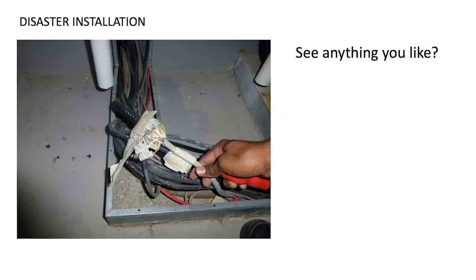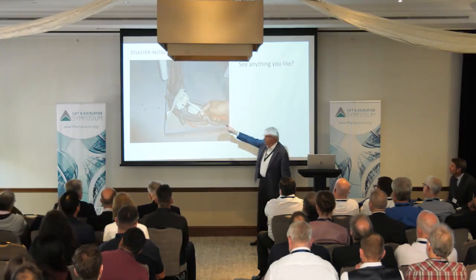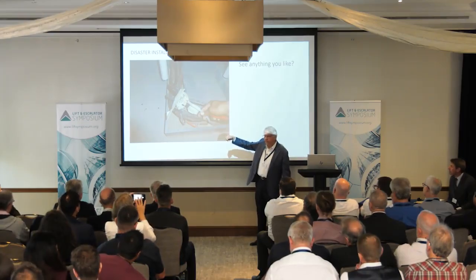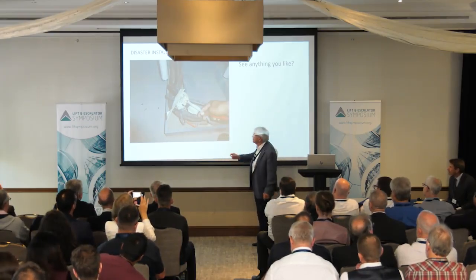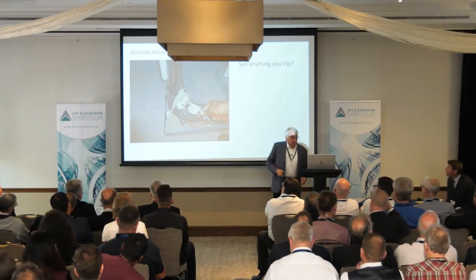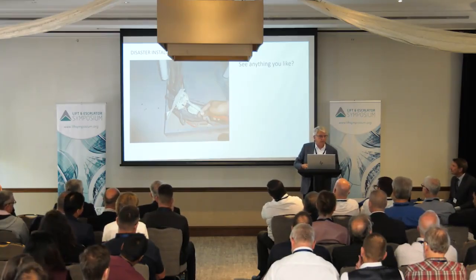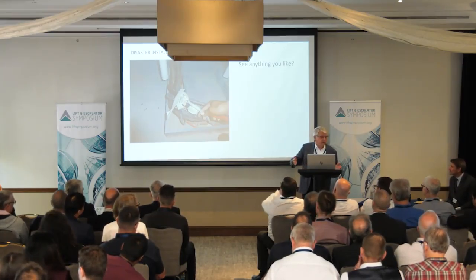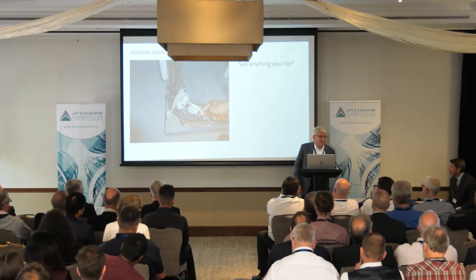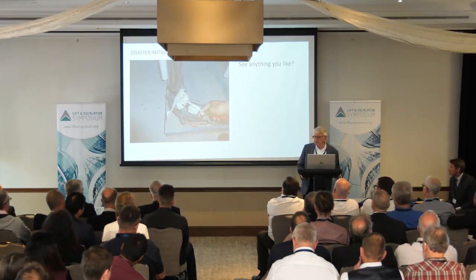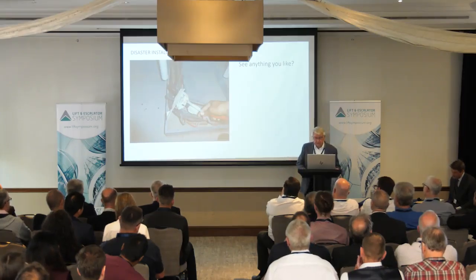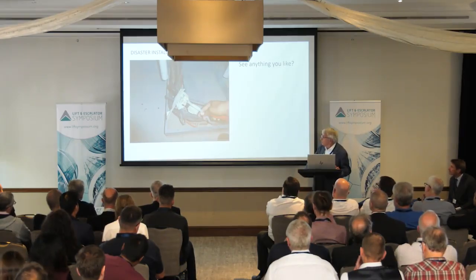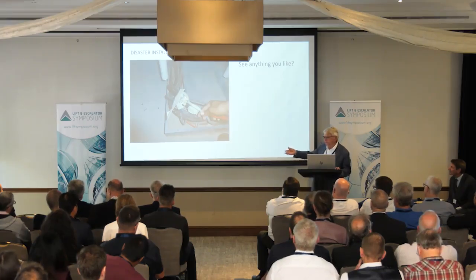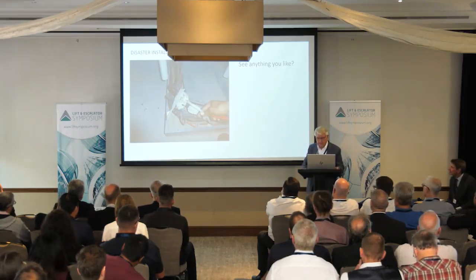The man here is holding encoder wires that were joined together inside the troughing, using masking tape as insulators. Then you see these black flexible conduits. You can always run a flexible steel conduit inside a troughing for good insulation, but these happen to be plastic, so they have no insulation whatsoever. It's a way to keep the wires physically separated, but only by a millimeter. It was a complete disaster, so we had to completely rewire this and separate the high and low voltage. You never want to make terminations inside a conduit or trough, because it's bad practice and causes a lot of trouble.